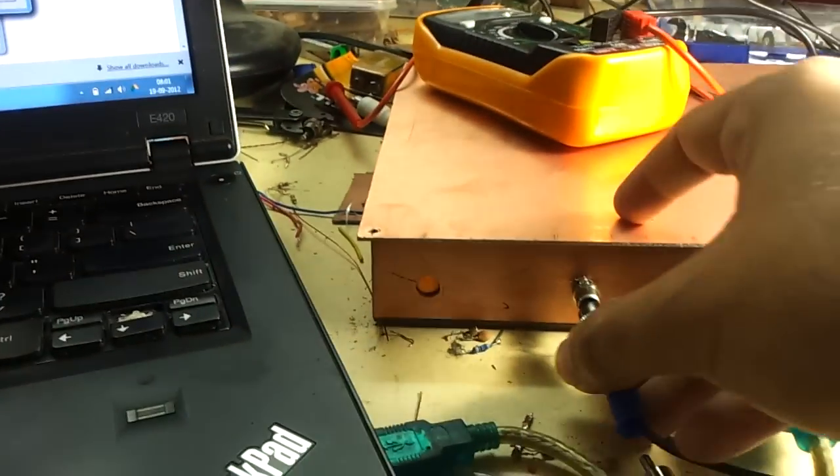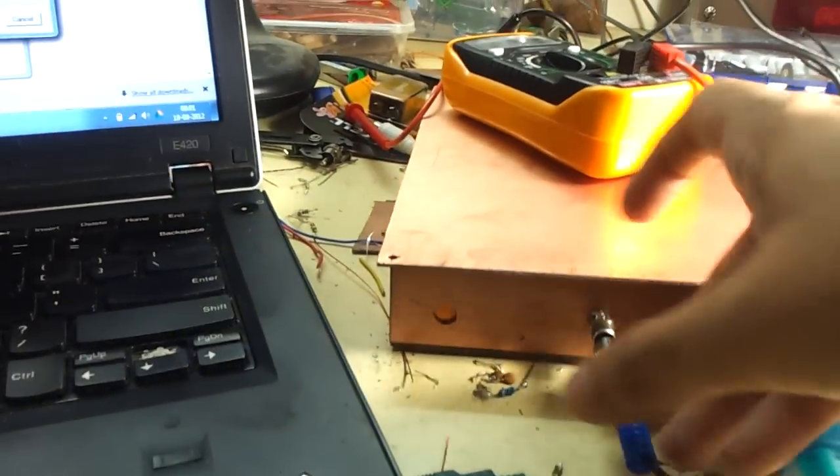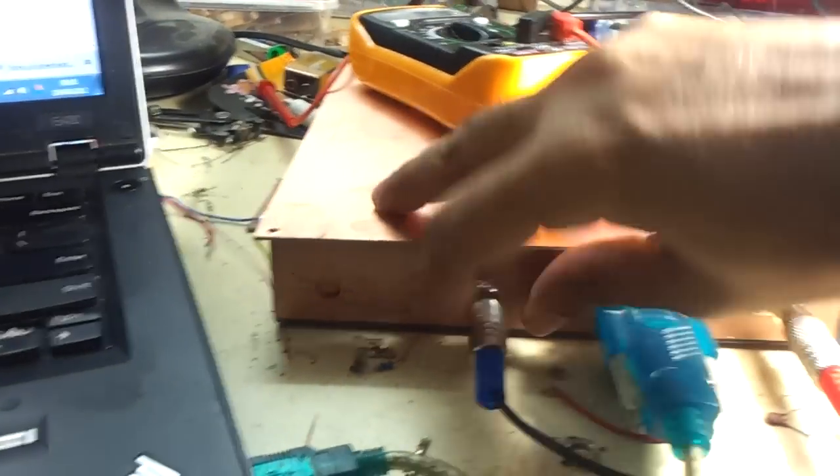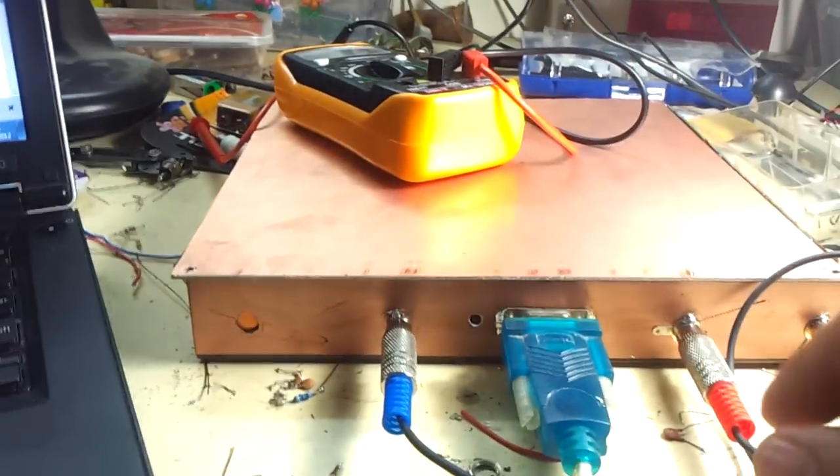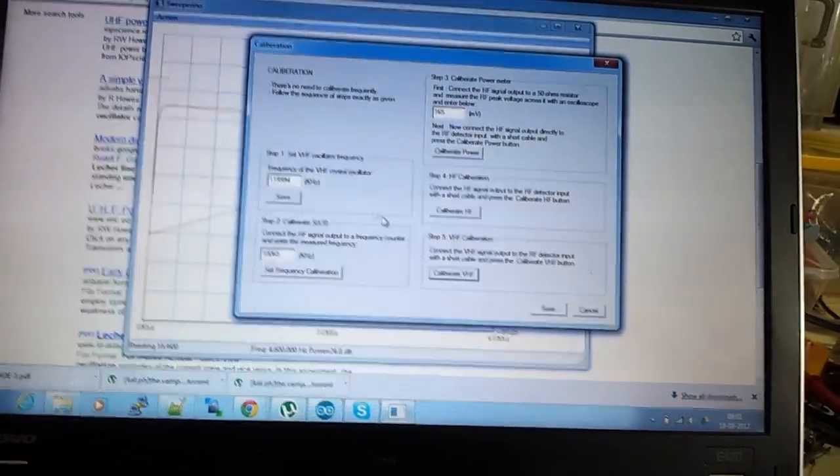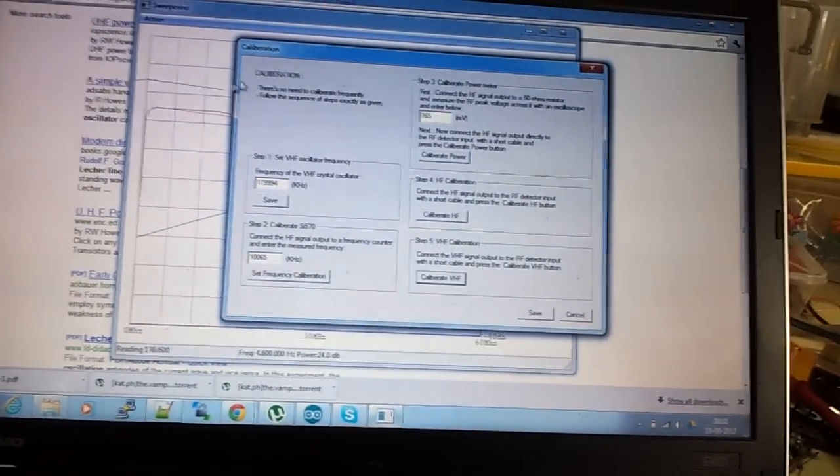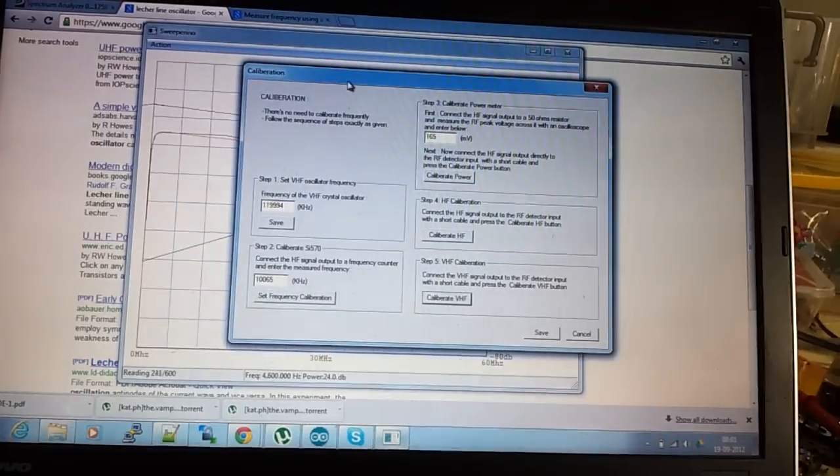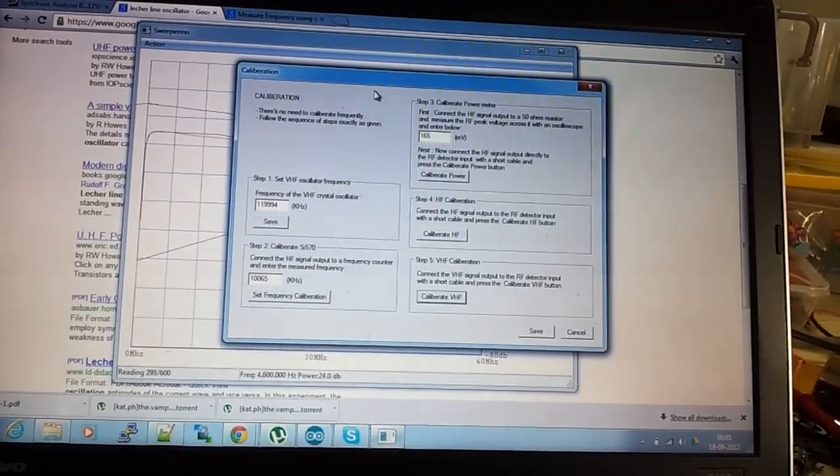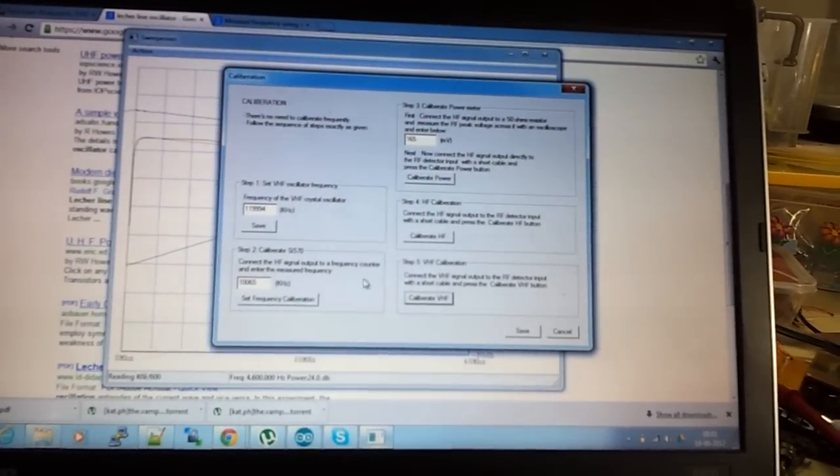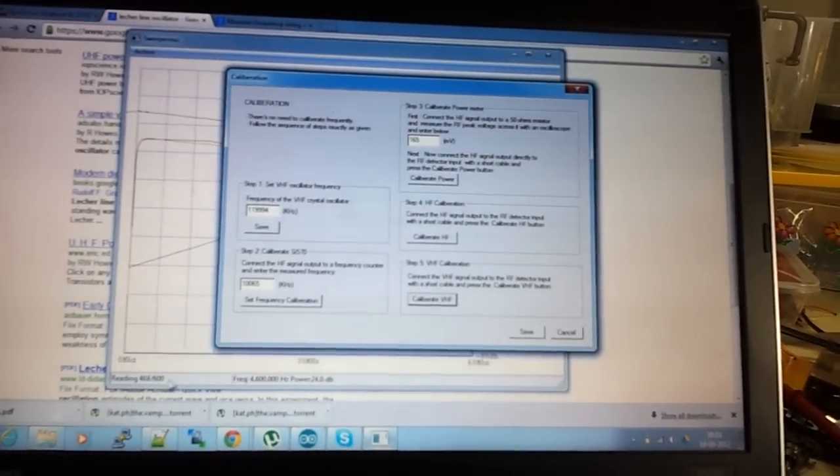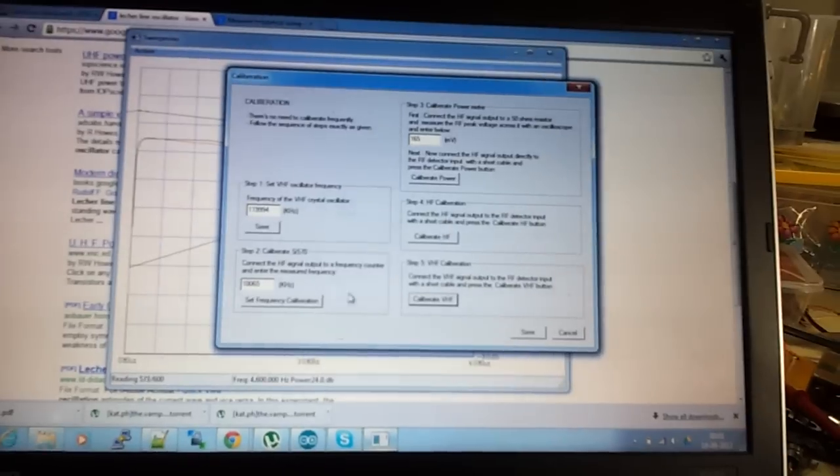Next we calibrate the VHF. So I connect the VHF output to the detector now, that's done, and run the VHF calibration. Now it measures everything here, but if you see the VHF calibration, that's not going so smoothly. I'll show you the curve in a bit as soon as this completes.